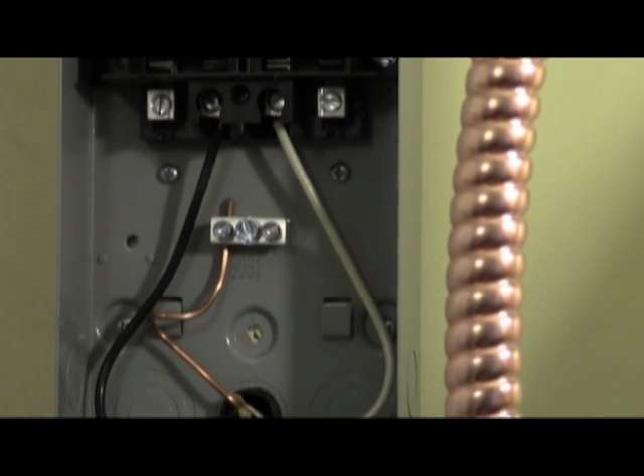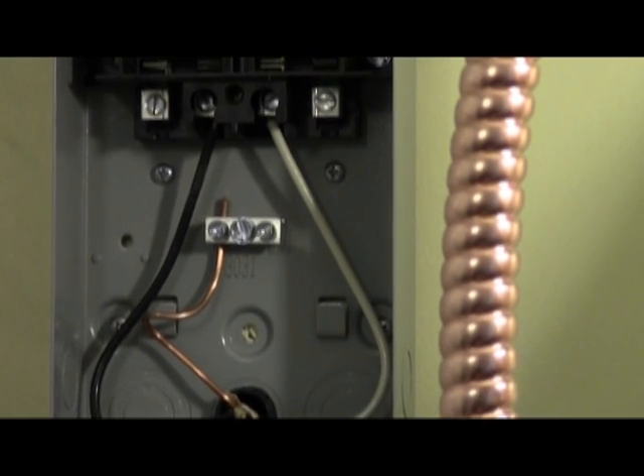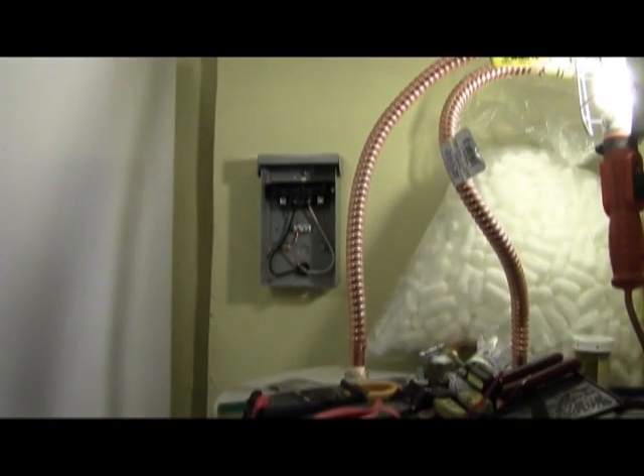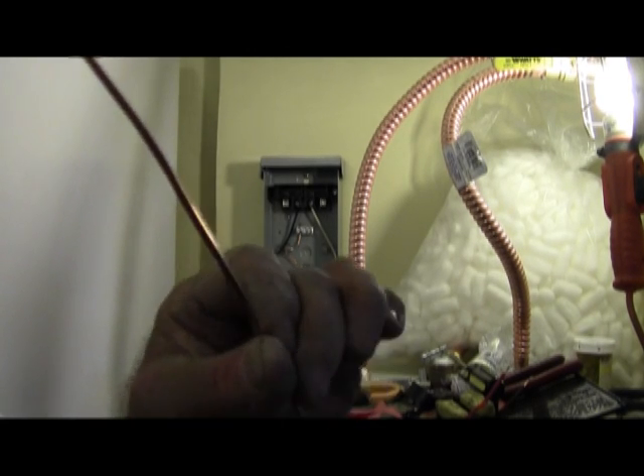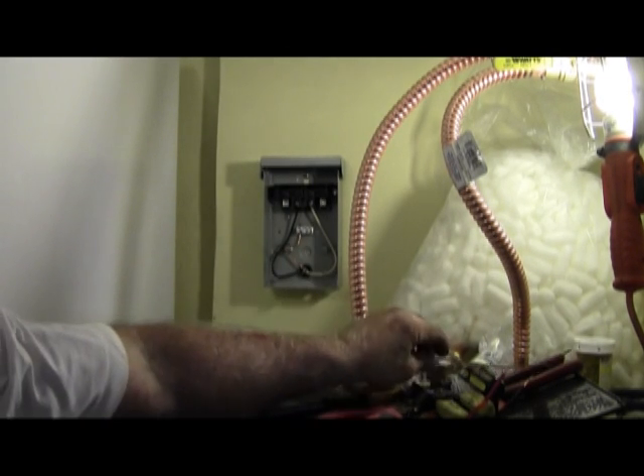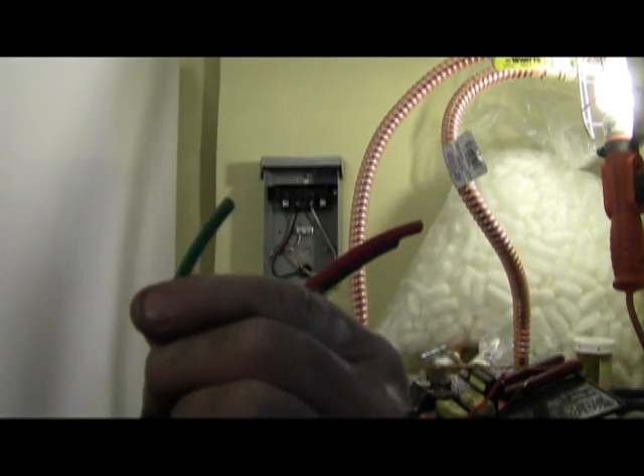You'll notice that there's bare copper for the ground, which was used in the Romex, but we cannot use that in the new whip because of the dissimilar metals code. So this wire has to be replaced with THHN stranded green.